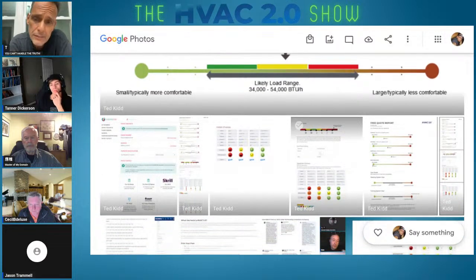So I either need to replace ductwork if I go with the same size in order to get the static pressure down, or I've got to go down in equipment size and take a little bit of risk that I may need to tighten the house up some if I have comfort issues on the hottest and the coldest days. Yes.